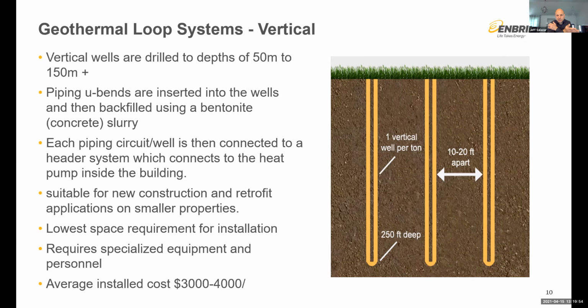Typically, we would drill a single bore per ton. Sometimes you can do 2 tons of capacity per borehole. And there is a separation between the bores depending on the conductivity of the soil and the quality of the soil. We will separate them typically 10 feet minimum, sometimes 20 to 25 feet apart. And again, the heat exchanger is sized according to the load on the building, the heat pump capacity, and the conductivity and qualities of that soil.